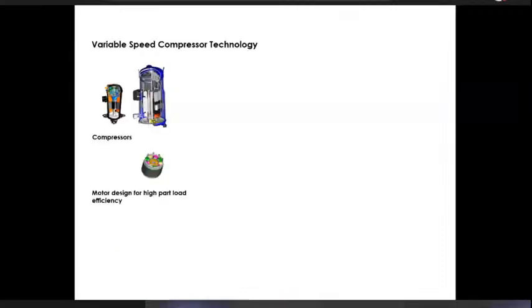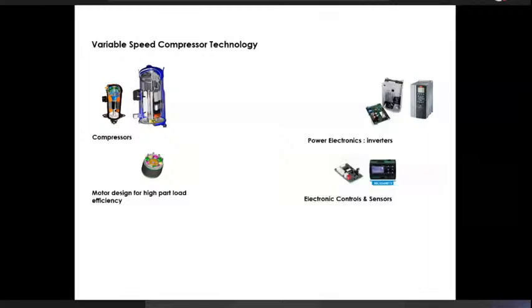Now when we look at variable speed compressor technology, we need to look at motor design for high part load efficiency. If we use a standard squirrel cage motor, its part load efficiency is very poor. So we need a motor designed for higher efficiency across the range of operation. Then we need inverters, some controllers and sensors, and a matching of all these components. So a lot of intelligence needs to be built in.